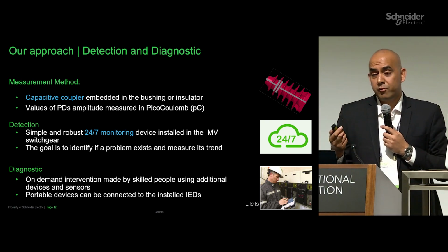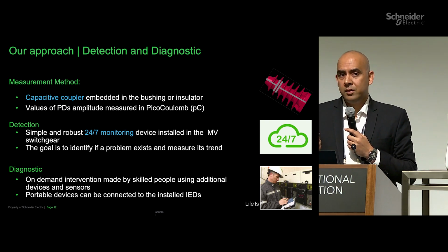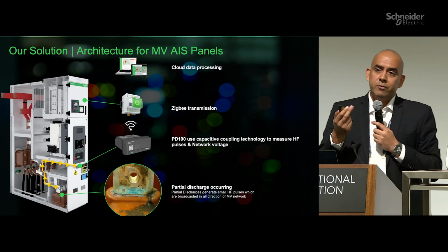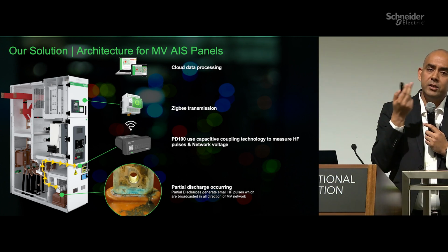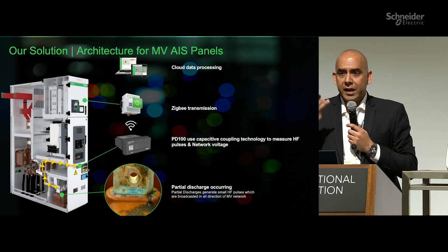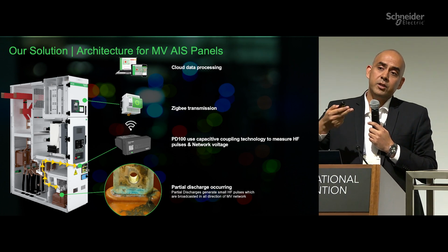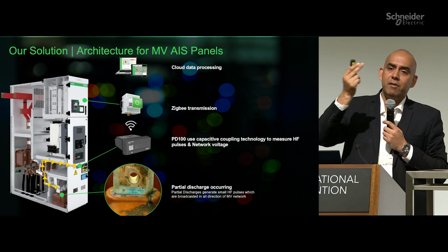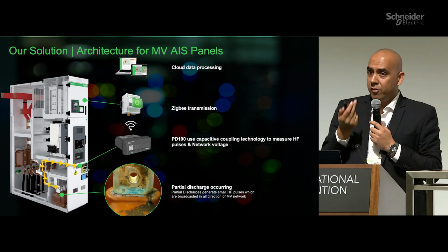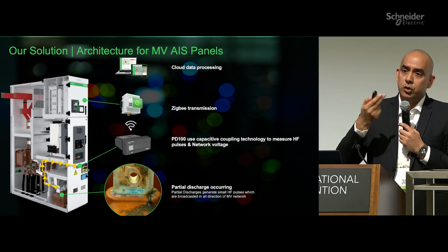So we have a capacitive coupler, which measures the partial discharge in picocoulombs, highly accurate, and we have a 24/7 monitoring system. So it is measuring the whole partial discharge, and plus we have our diagnostics. That means the analytics which are running, which are able to detect if there is an issue which is developing inside the system. And we are able to give advisory to you to do a detailed check. Suppose there is an issue which is coming in the system, we're able to do a detailed check through detailed diagnostic systems, etc. We can get in front of the panel and have a check in a detailed way during our maintenance calls. So this is our approach.